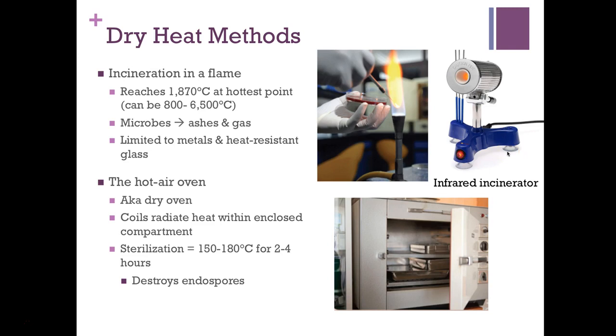The hot air oven, also known as a dry oven, has coils that radiate heat within an enclosed compartment. Sterilization takes place at 150 to 180 degrees Celsius for about two to four hours, which destroys endospores. It is used for glassware, metallic instruments, powders, and oils. Avoid using it on materials that burn at high temperatures, such as paper, cotton, or plastic.